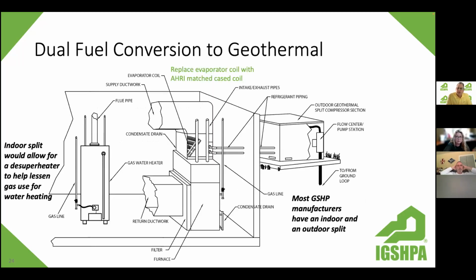This would be a dual fuel conversion to geothermal. Just about all the manufacturers have an outdoor split like this, but it doesn't get used very often. If we were to look at this outdoor split installation, you can see nothing changed inside this mechanical room. We would have to update the A coil here, the cased coil, to an AHRI match, but for the most part, it's going to be roughly the same size, likely. So we don't have a lot of ductwork modification. We keep the same gas lines, the same venting, water heater if we like, especially if it's 100 amp service, we may not have a choice.